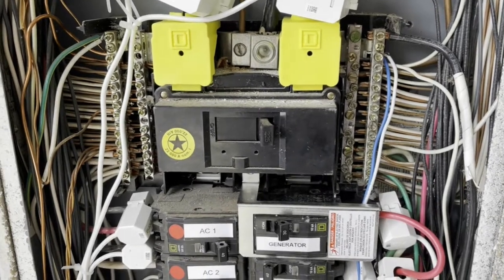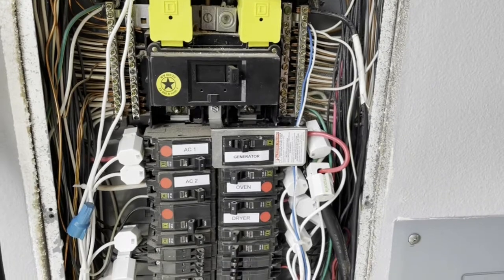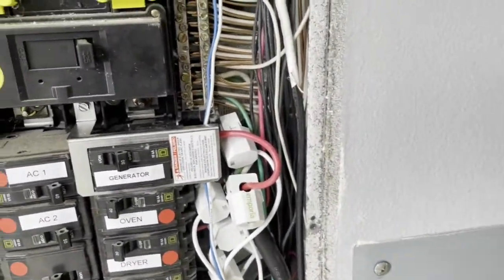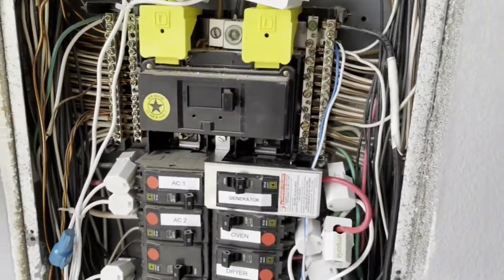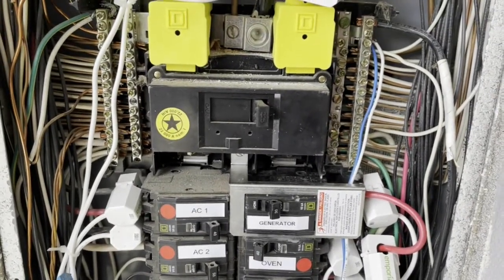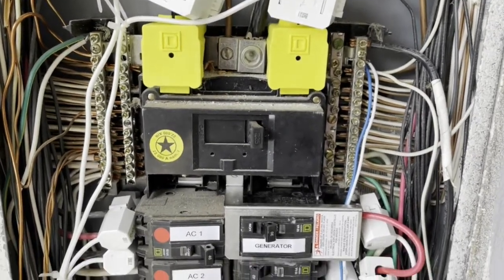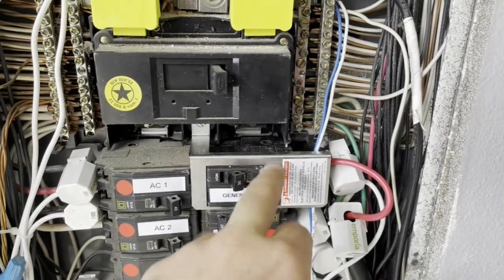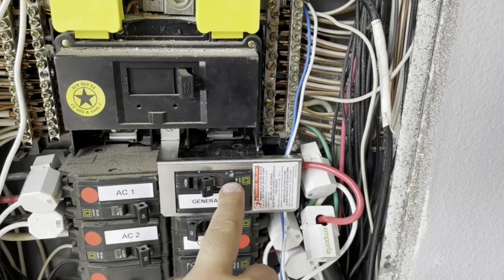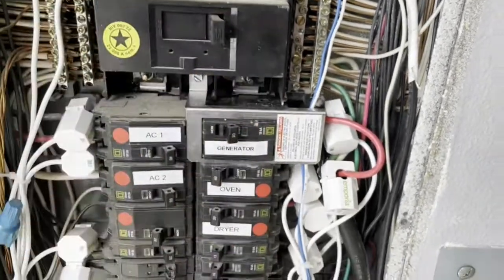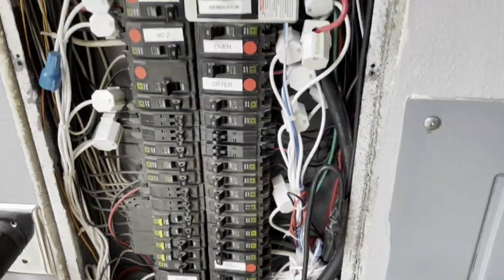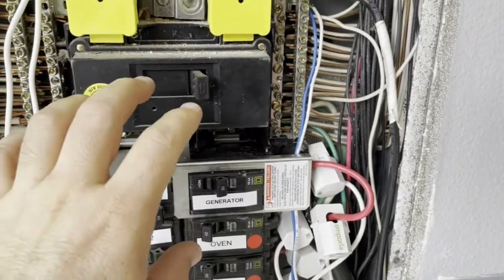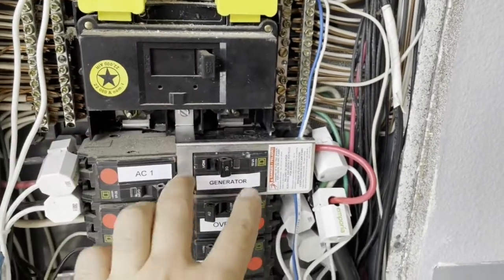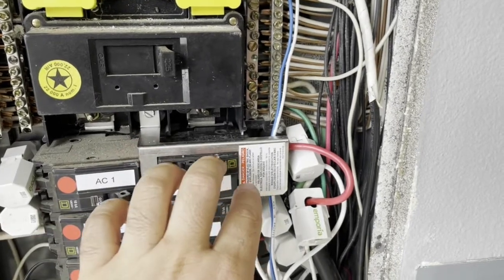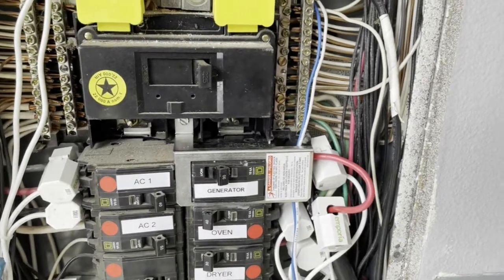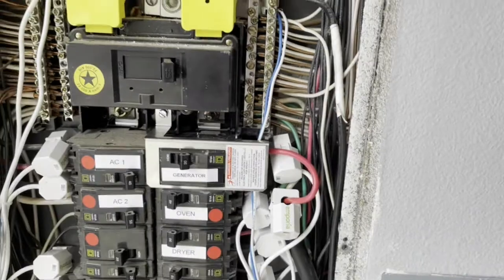In most houses, the neutral and ground come together in the main panel and become one. So once you use the power, it's drained over these ground and neutral wires. So I showed you the Interlock Kit. That Interlock Kit must be compatible with your main panel. This is a square D QO panel, 200 amps, and if your main switch is up, then the generator circuit breaker must be the right top circuit breaker. If your panel is upside down, then of course it will be the lower bottom left one. The reason is that the Interlock Kit is specially designed for this panel so that it can really control these switches. This also comes from that kit, so it prevents people opening this panel during emergency operation or regular hours, and there are warnings on it about the dangers.